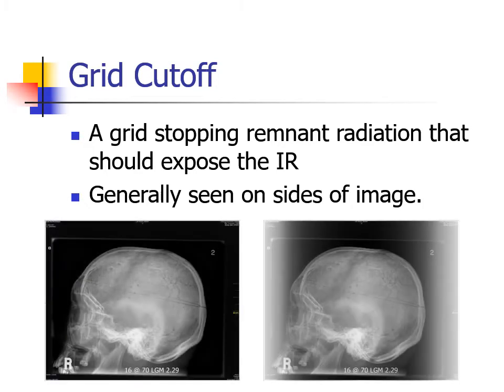The one on the right is suffering from grid cutoff. Notice the white borders in the front and behind the skull caused by the grid stopping information-carrying radiation from reaching the image receptor.